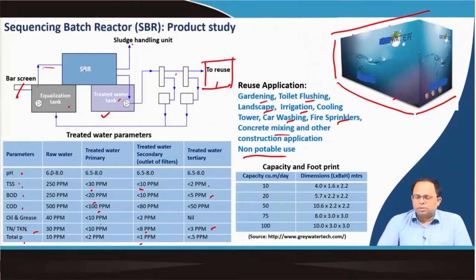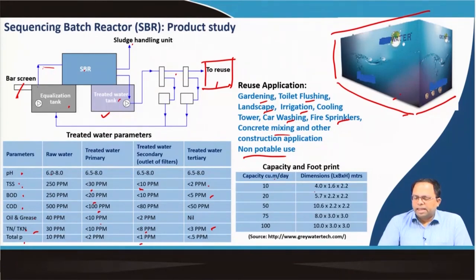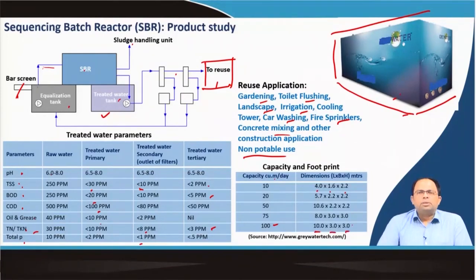The size of a commercial SBR unit: to treat around 10 cubic meters per day, the size can be as small as 4 m × 1.6 m × 2.2 m — very compact. For around 100 cubic meters per day, the dimensions come to around 10 m × 3 m × 3 m. That gives you an idea of the compactness of this kind of system.